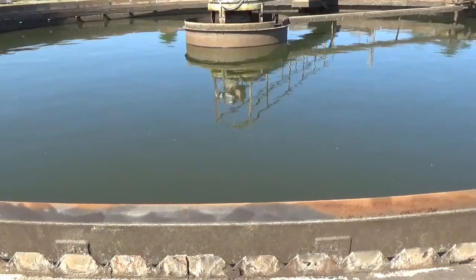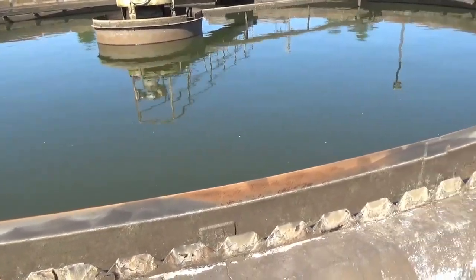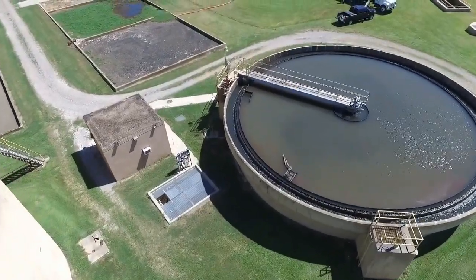It's pumped from the grit chamber, comes down, and goes into the primary clarifier. What it does is pump it in there with a scraper that continuously turns, knocks the trash, and the trash settles.